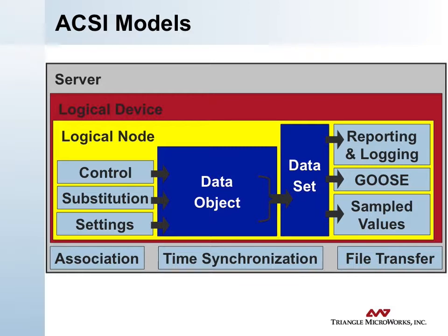Within each logical device there is a set of logical nodes. At the logical node level, you have control capabilities, substitution, and parameter settings, which operate on a set of data objects within the logical node. These data objects can be organized into data sets. Data sets can be arbitrary types and organization of data, but they define a group of data objects for the purposes of reporting and logging services, GOOSE (the generic object-oriented substation event), and sampled values.